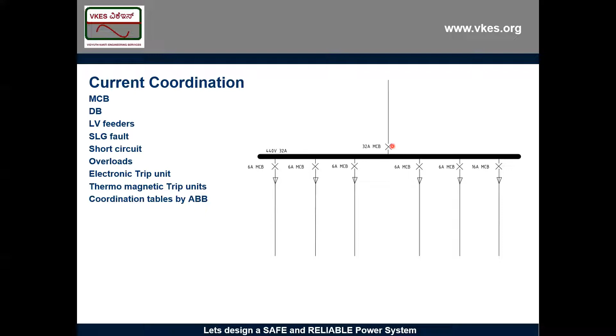And when I combine all these, the size of the incomer breaker is not the addition of all this. I have to write down my load schedule. I have to prepare a schedule, and there I have to determine the total power consumed by this house or building, and then I have to determine the incomer breaker rating. I have to take all the load factors. When I take those factors, the rating of this breaker will come less. Am I correct, Mr. Pinaki? Yes, sir, you're right, sir. It's a diversified load at the panel level. Clear, Mr. Inamul? Yeah, I understood, sir. Okay.